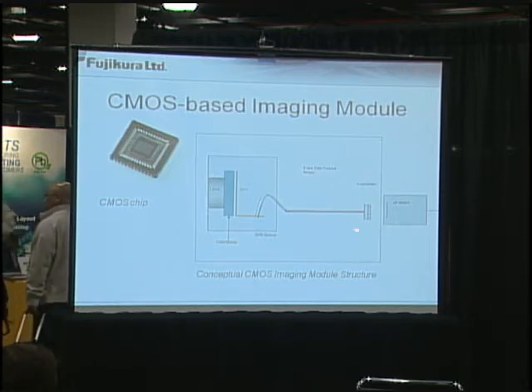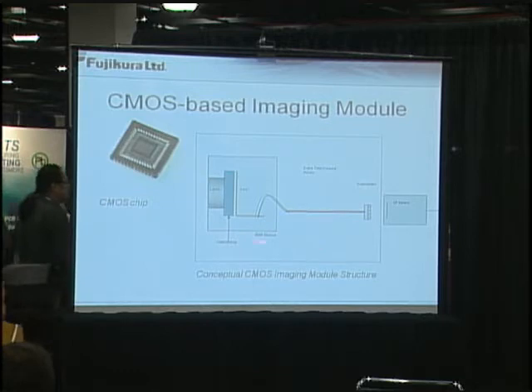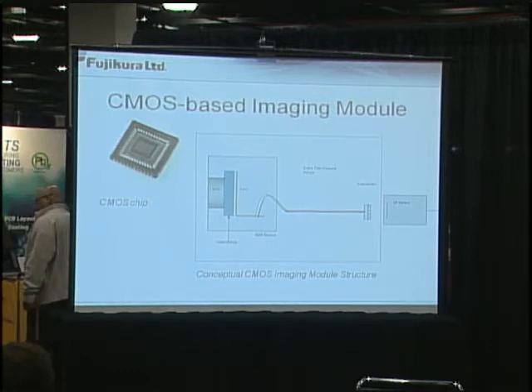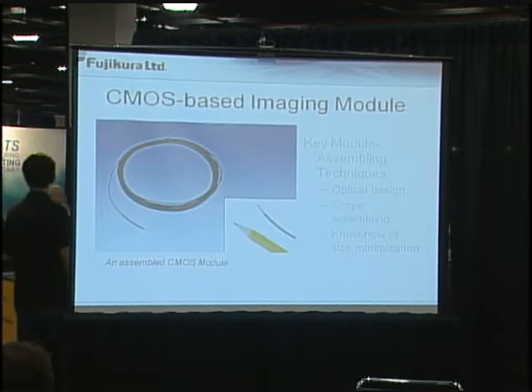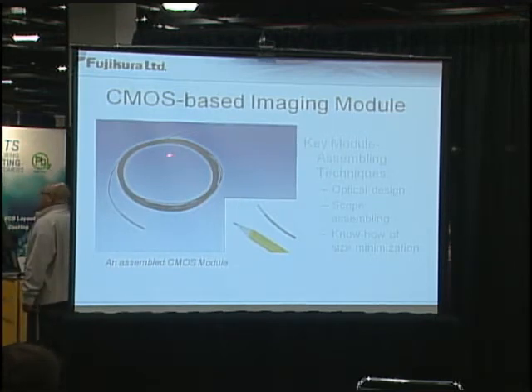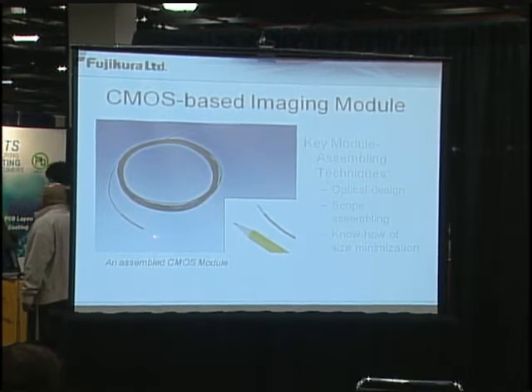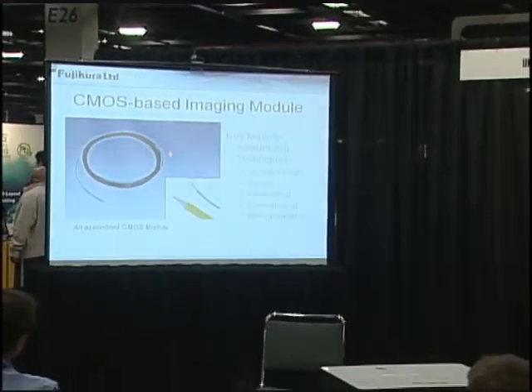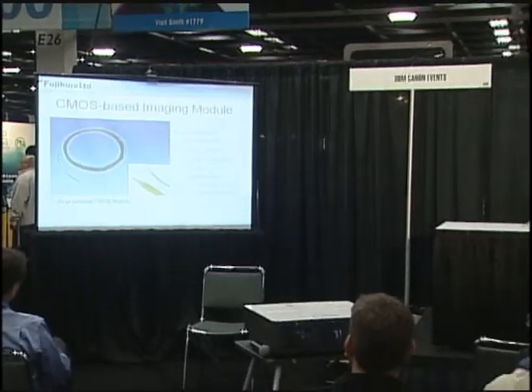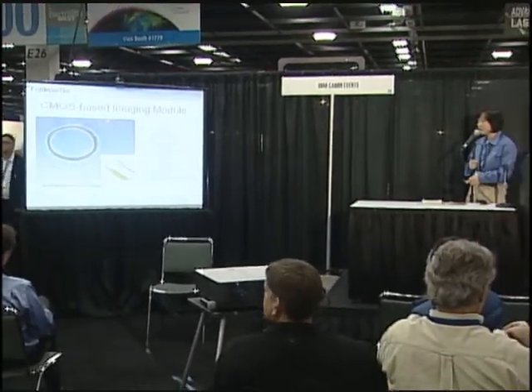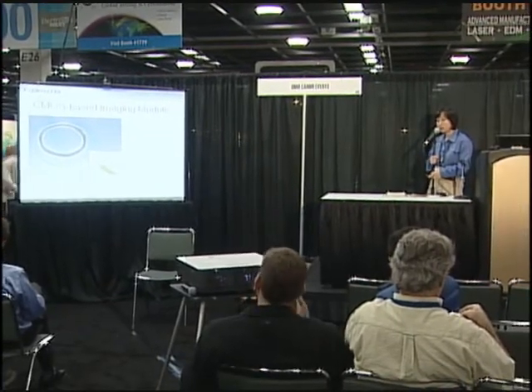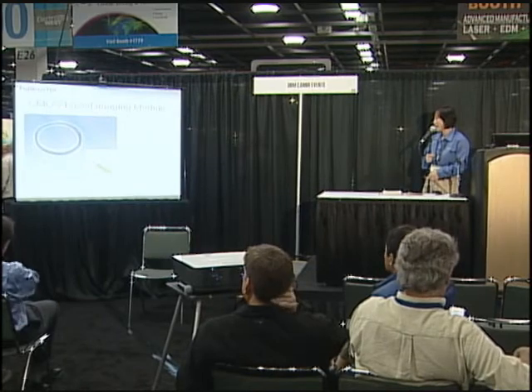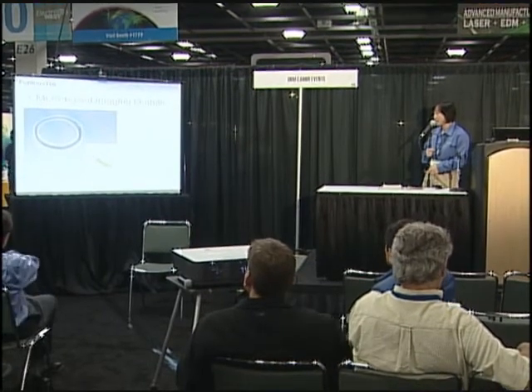The next slide gives you an actual picture of the CMOS module, which is also the example I passed around. This is a distal tip with the optical lens. These are the electric wires — coaxial cables — which can run up to four meters long. On the back end, you may have a connector, which allows you to connect it to an interface board. This is the size comparison to a pencil tip.